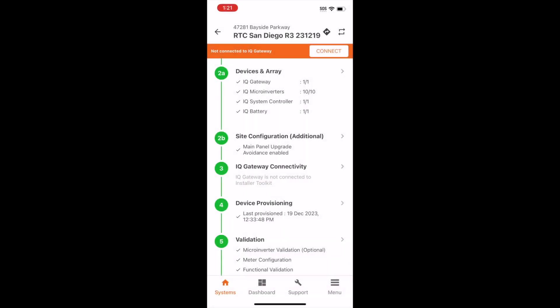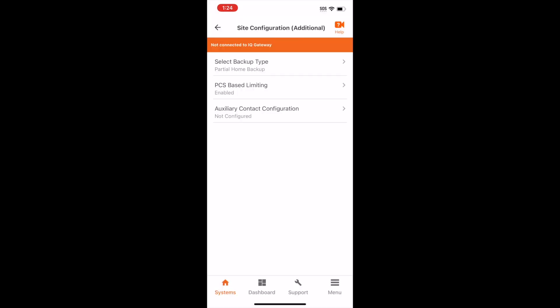IQ Battery Oversubscription allows more Enphase battery storage at a given site, and also allows more batteries per circuit by carefully managing the power output. Similar to the previous steps, after selecting the site, look at the main menu and select Site Configuration Additional, sometimes referred to as Advanced Features or Additional Configuration Options. Select PCS Based Limiting.